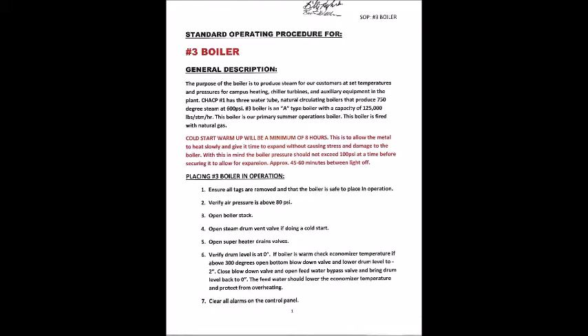Placing number 3 boiler in operation. Step 1. Ensure all tags are removed and that the boiler is safe to place in operation. Step 2. Verify air pressure is above 80 psi. Step 3. Open boiler stack. Step 4. Open steam drum vent valve if doing a cold start. Step 5. Open superheater drain valves. Step 6. Verify drum level is at 0 inches.